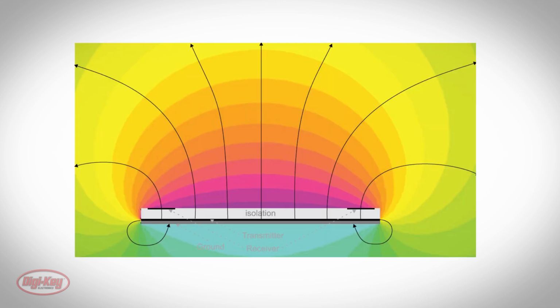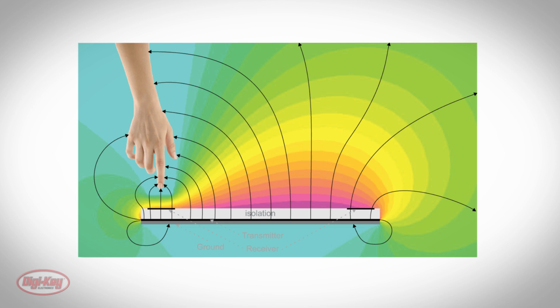Electrical near fields, or E-fields, are generated by electrical charges and propagate three-dimensionally around the surface carrying the electrical charge. When an alternating voltage is applied, the resultant E-field is also alternating. And when the alternating wavelength is much larger than an electrode geometry, the result is a quasi-static electrical near field that can be used for sensing conductive objects, such as a human body. For example, when the operator's hand intrudes into the E-field, the field becomes distorted. Specifically, the field lines interrupted by the hand are shunted to ground through the conductivity of the human body itself. As a result, the three-dimensional electric field decreases locally.